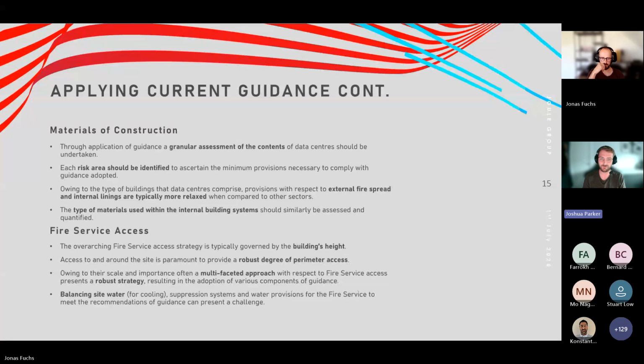So how do we look to overcome that? We often try to present a multifaceted approach, with perimeter access as best as can be achieved. Often we try to push for modification to the access route to increase perimeter access, alongside the provision of dry or wet rising mains to support the fire service in entering the building, rather than fighting the fire defensively, giving them multiple directions of attack, particularly where we've got gantries, rooftop located plant, and increasingly multi-story data centers.